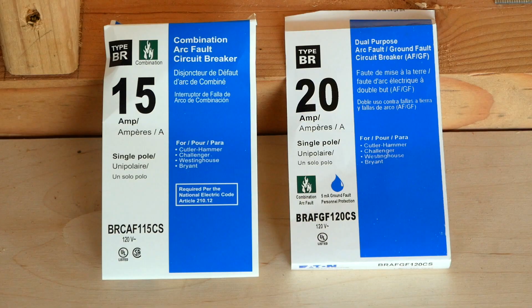And I think they are especially important for tiny house builders because tiny houses could be potentially prone to a ton of vibration while they're traveling down the road, which means the chance of loosening a connection and having an arc fault just goes up exponentially. Now, arc fault circuit breakers are hugely expensive, and if you get the combination arc fault dual function ground fault circuit breakers, they can be upwards of $50 a pop. But when you consider how few circuits are in a tiny house, that's just an extra $150 for a huge amount of extra life safety.